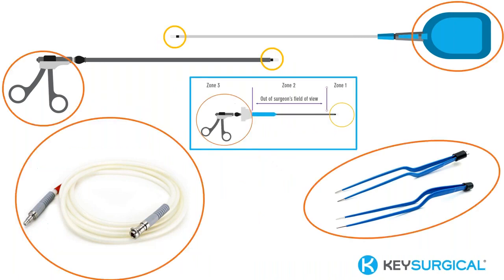So Michelle just mentioned the 3 zones of the instrument. Zone 1, which are the yellow circles you can see here on our slide, and zone 3, which are the orange circles, are visible during her procedure. As you can see, some of the instrumentation is fully visible during a procedure, but like Michelle mentioned, things still get missed. And as we know, there's a lot going on in a procedure. So it's important that sterile processing inspect each area we just discussed.